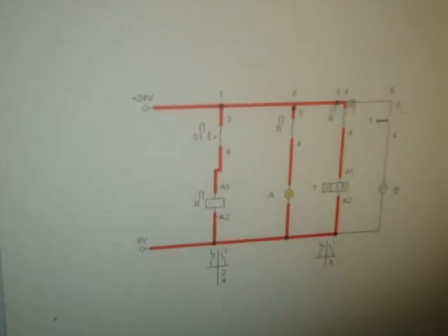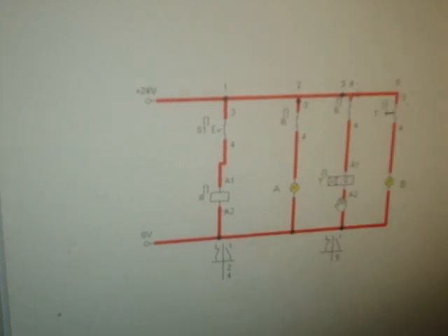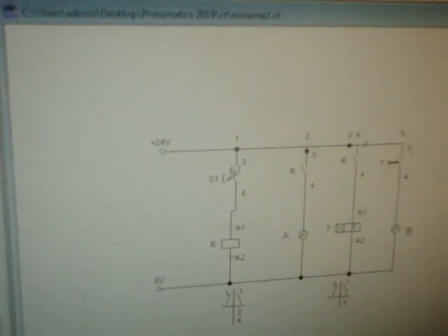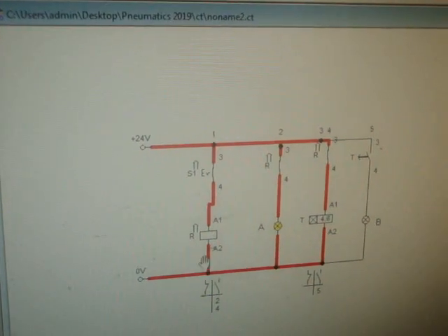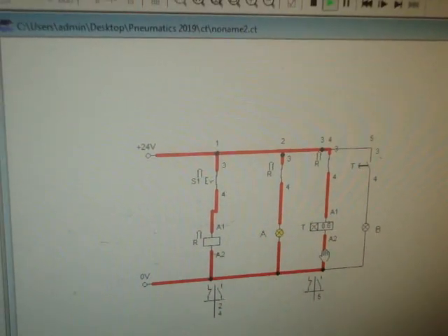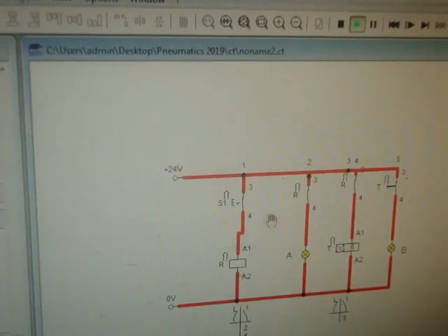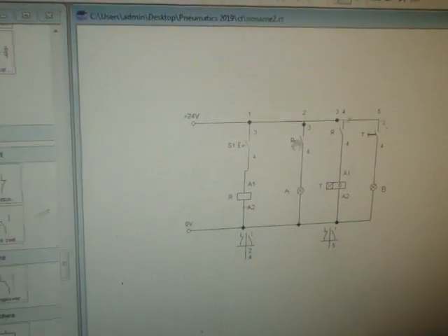First, bulb A will be on. The relay is on. Then the on-delay timer starts — set to 6 seconds. After 6 seconds, bulb B is on. When I turn off S1, both bulbs turn off at the same time, because it is an on-delay timer. Once again: bulb A is on, relay is on, on-delay timer starts, after 6 seconds bulb B is on. When off, both turn off at the same time. This is called on-delay timer.